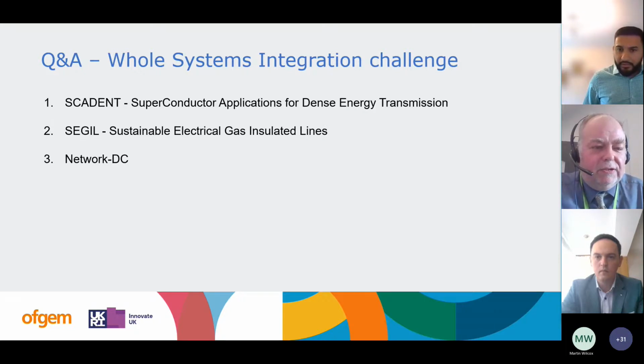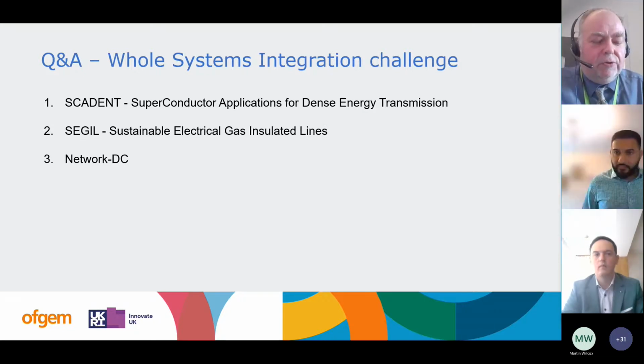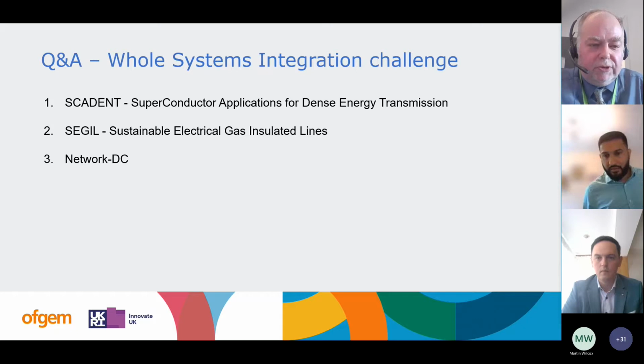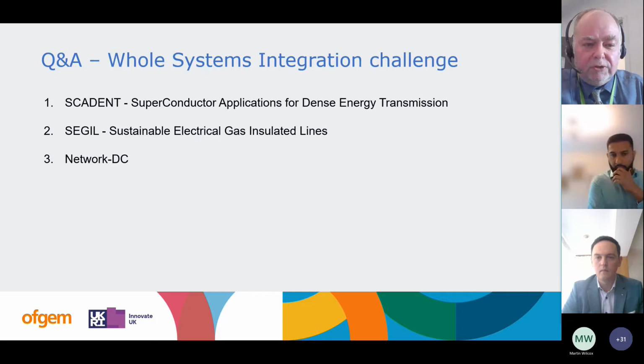Yeah, so this is it. The approach of turning the whole DC network arrangement off and then switching it back on again is an option, and you do that via these high-speed switches, which identify where the faults are and how to isolate the network quickly. But to do that, you need communications, and you need to deal with the mechanical timeframes of these selectors, and that all takes time. So it's taking seconds, and the problem with a frequency event is you don't have seconds.